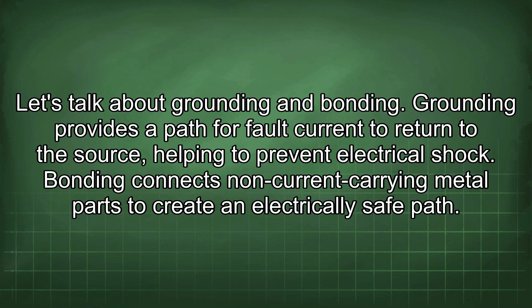Bonding connects non-current carrying metal parts to create an electrically safe path. In older homes, grounding and bonding may be inadequate or non-existent. Upgrading the grounding and bonding system is often a critical step in improving electrical safety.